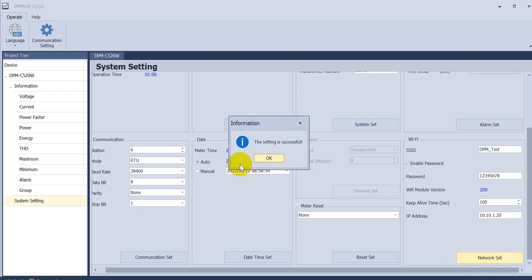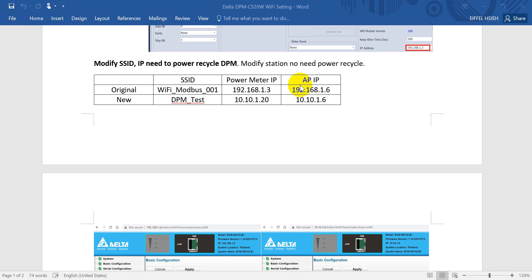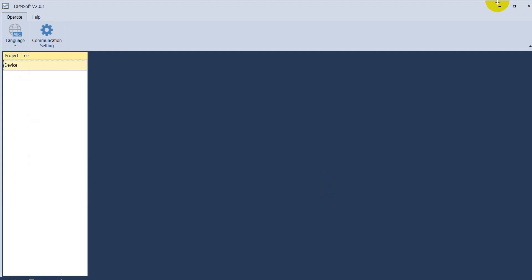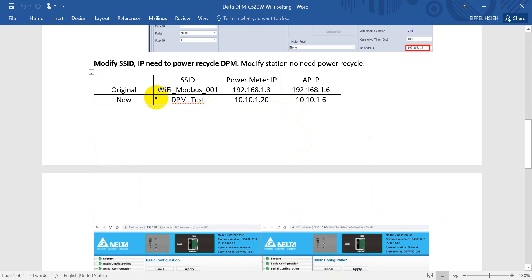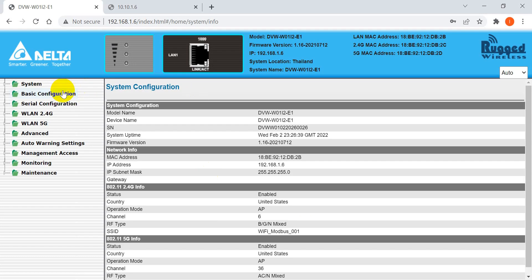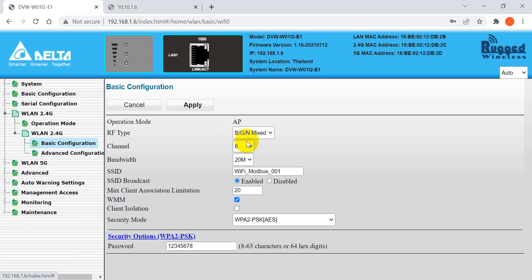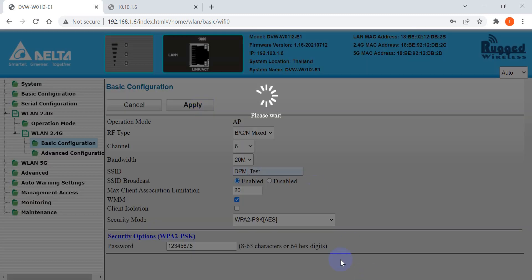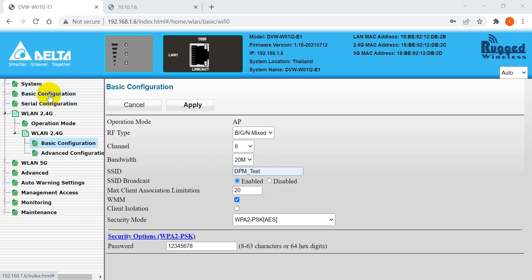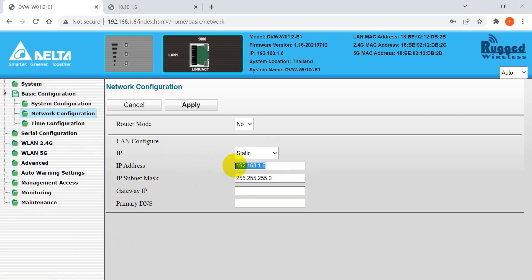Once finished, we have to power recycle the power meter. Next, we have to go to the access point and modify the SSID and the access point IP. We change the SSID to DPM_test and apply. After that, go back to the basic configuration and modify the IP address of the access point to 10.10.1.6, then apply.